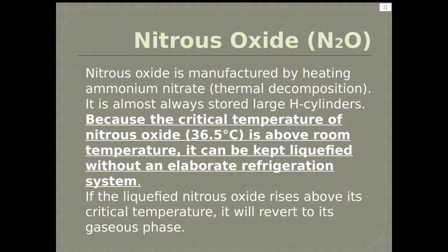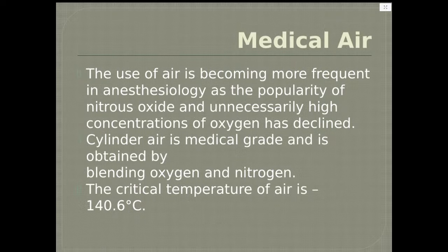Because the critical temperature of nitrous oxide is 36.5 degrees, which is above room temperature, it can be kept liquefied without an elaborate refrigeration system. If the liquefied nitrous oxide rises above its critical temperature, it will revert to its gaseous phase. And about medical air, in our hospital we are working with oxygen and medical air.